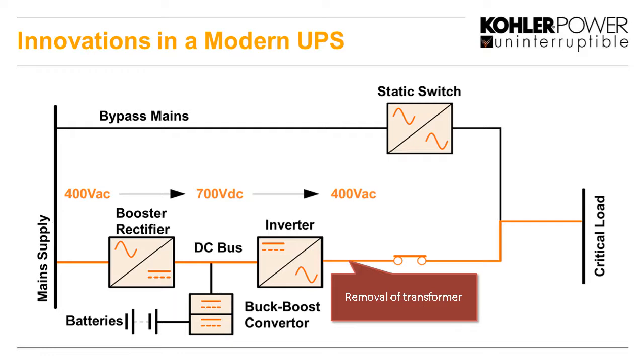We've seen some innovations with modern UPSs, and one of the main innovations over the last 10, 20 years has been the removal of an output transformer, which was in the output, and that was used to step up the inverter voltage to feed the critical load. And with modern technology, with the rectifier booster and inverter, we've managed to get rid of that, increasing the efficiency in that line, and also making removal of a big transformer, making it much smaller and lighter. With those changes, we've also had to improve the booster rectifier, and that's had a lot of benefits because we've had to increase the power factor, and typically nowadays the input power factor is unity, very close to unity. So that's actually made the harmonics and things like that going back on the mains much less and much kinder to the supply in the building.